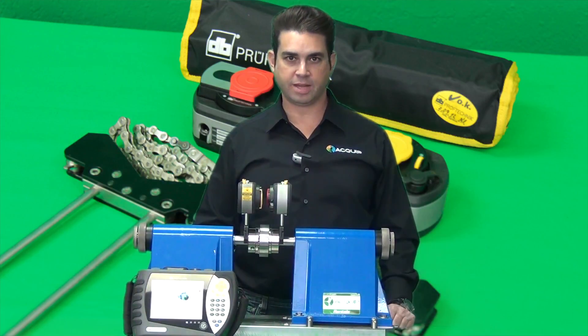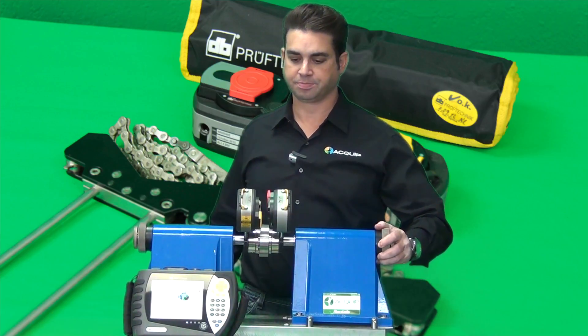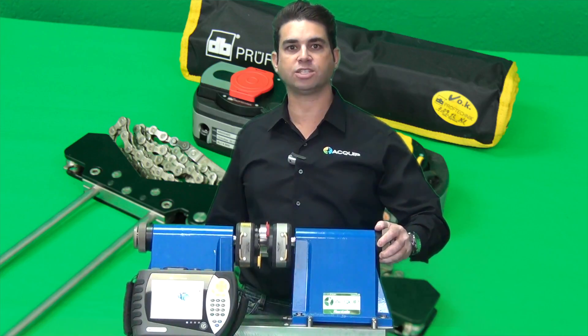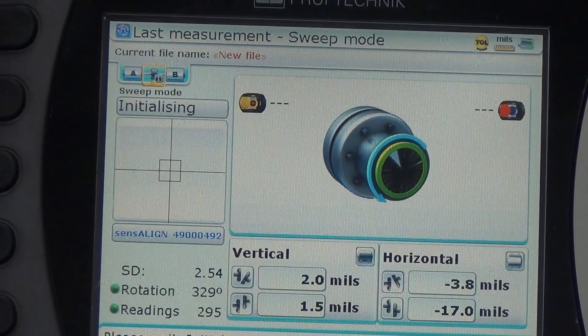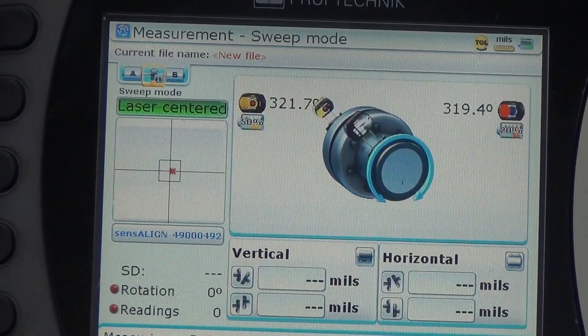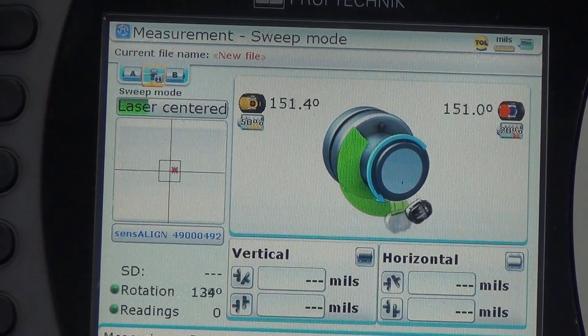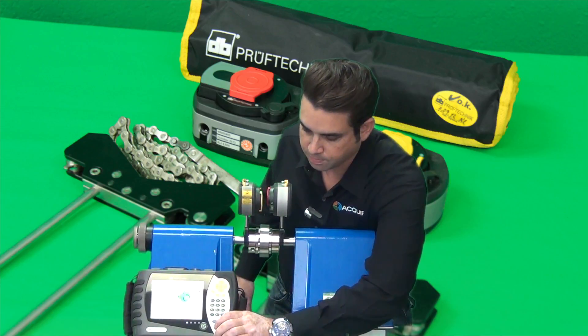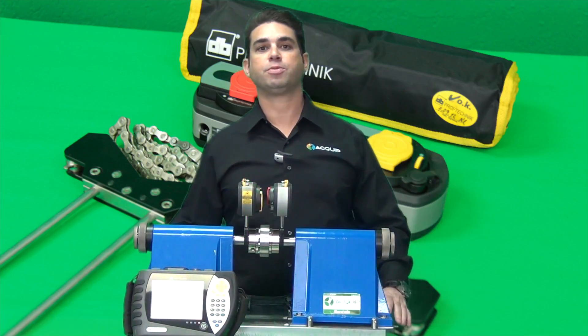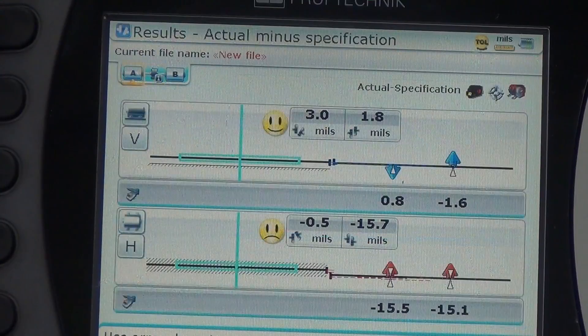After you've entered all the dimensions, you simply hit the measurements key and then rotate the shafts, and the ROTALIGN Ultra IS will automatically start taking readings. You want to rotate a full 360 degrees so that the tool can make the best decision possible based on your alignment. After you've rotated the 360 degrees, you press the results button and the computer will calculate the moves you need to make for horizontal and vertical alignment in order to have an ideal alignment.